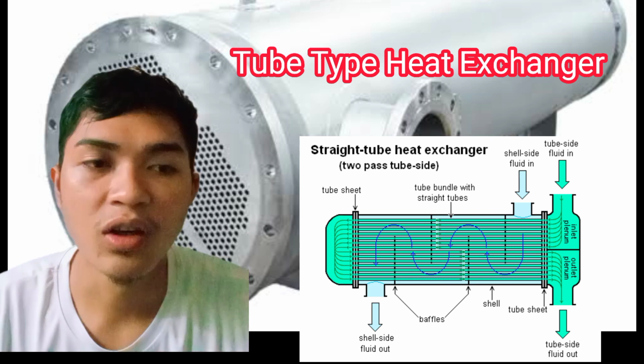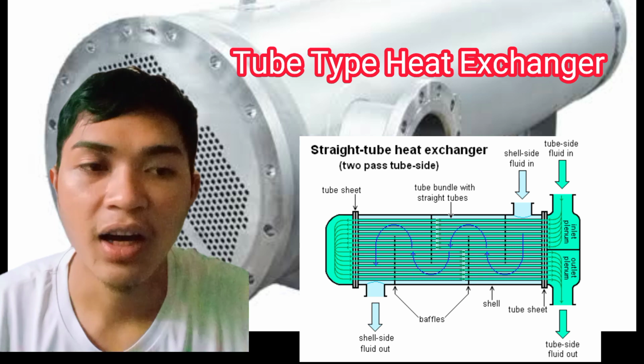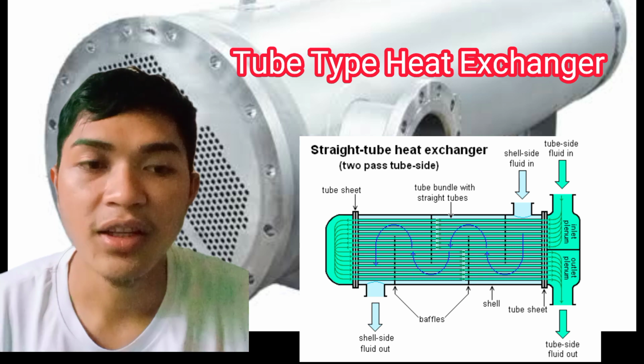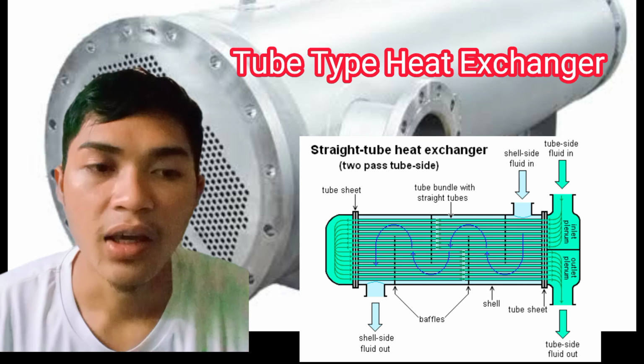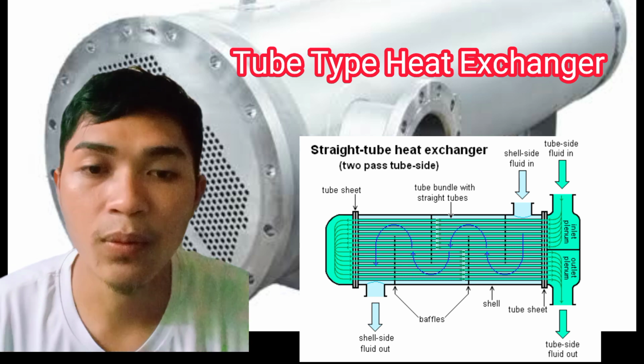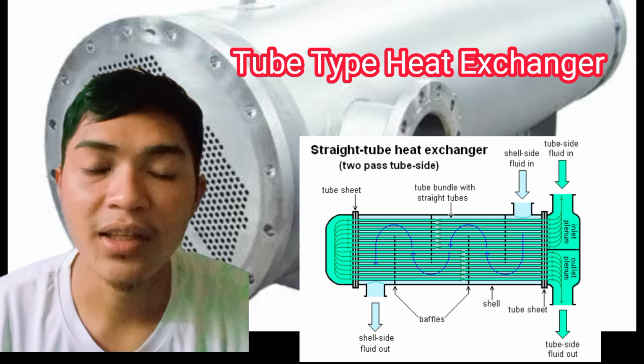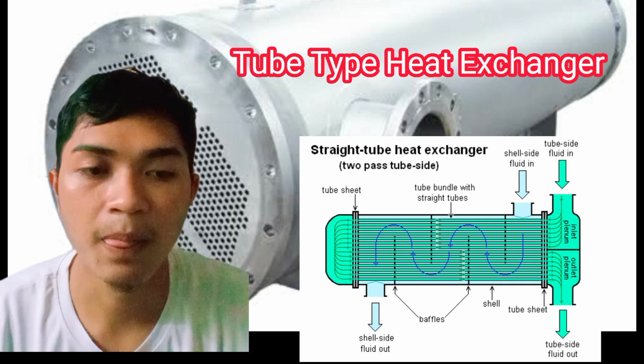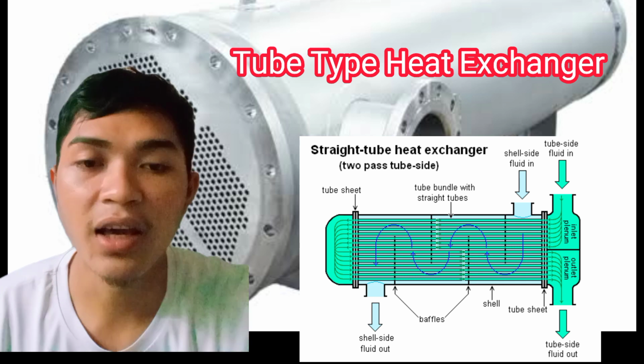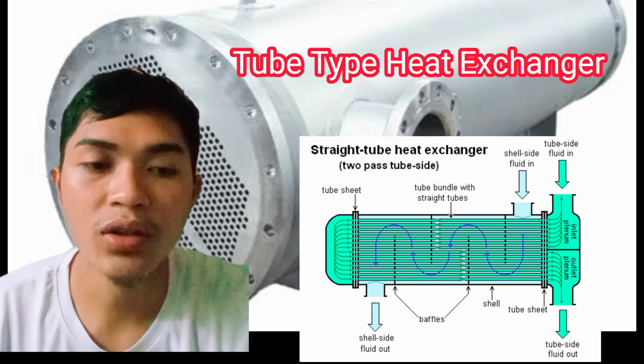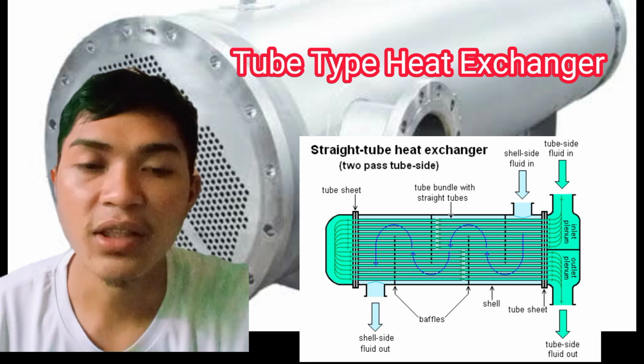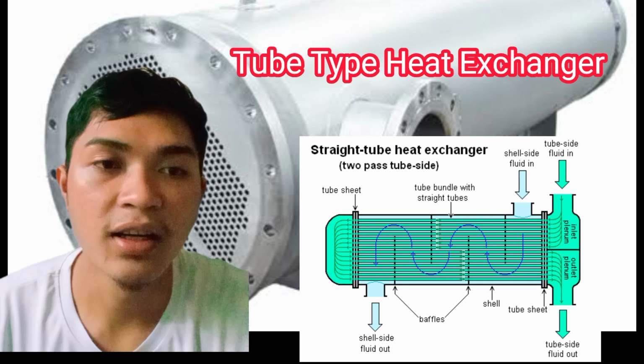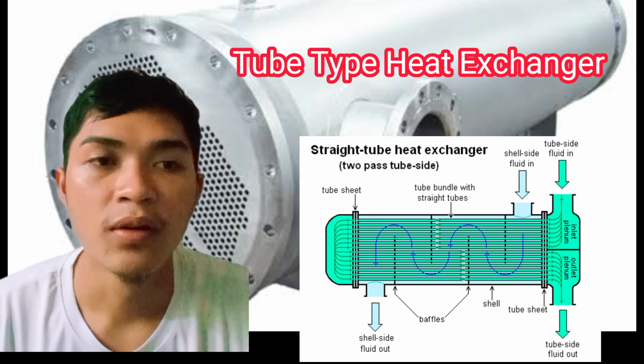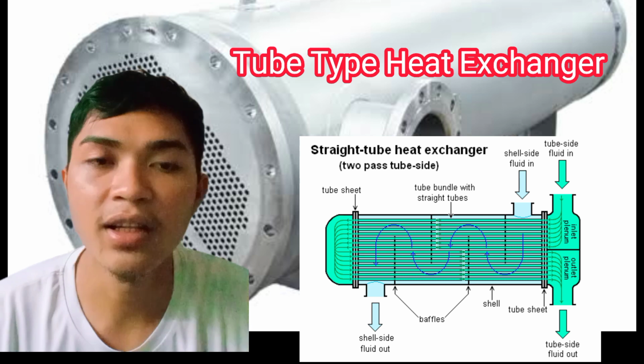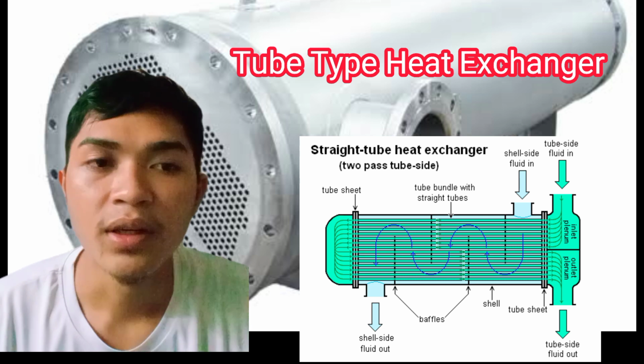If the deposits on the heat exchanger are not so hard, then they can be removed using a wire brush. If the deposits are stubborn, chemical cleaning should be used by immersion of the part in chemical solution. Depending on the type of the heat exchanger, there are tools provided by the manufacturers for the cleaning purpose. For example, there are special tools for cleaning shell and tube type heat exchangers.